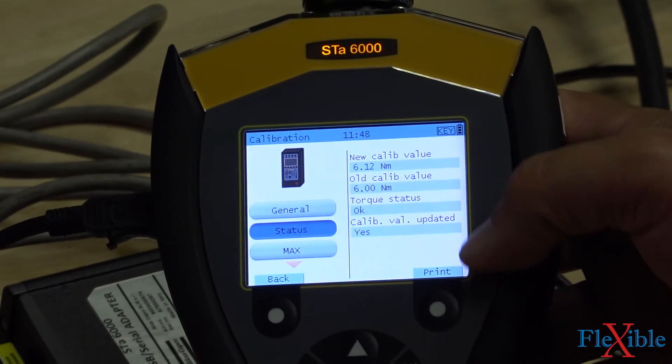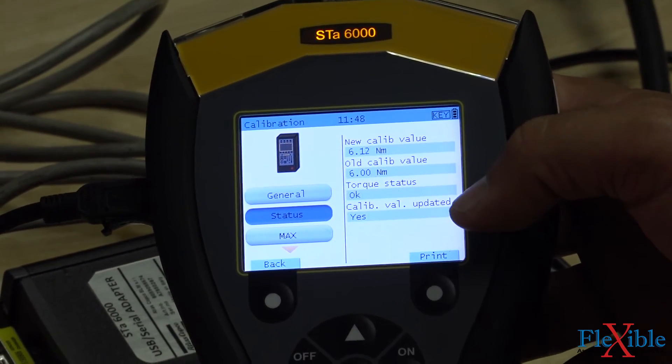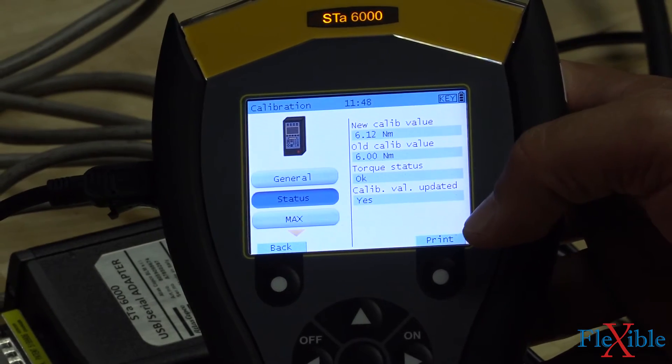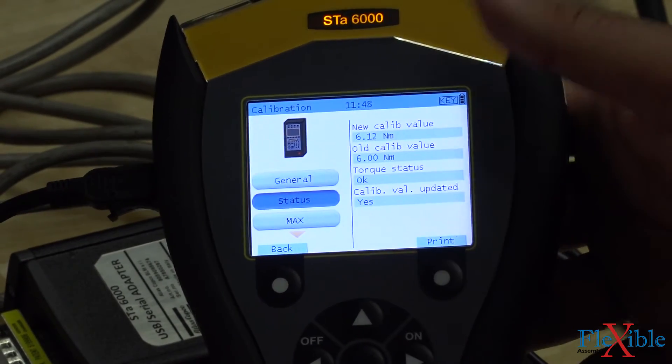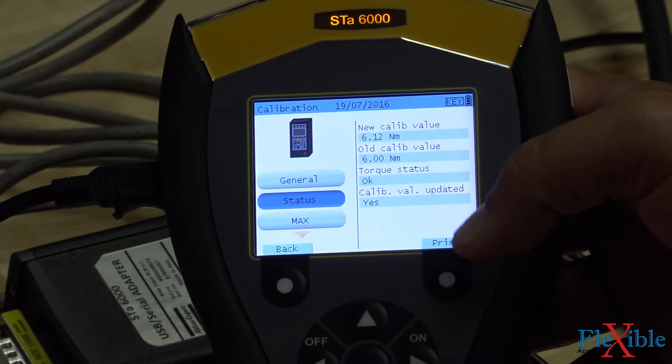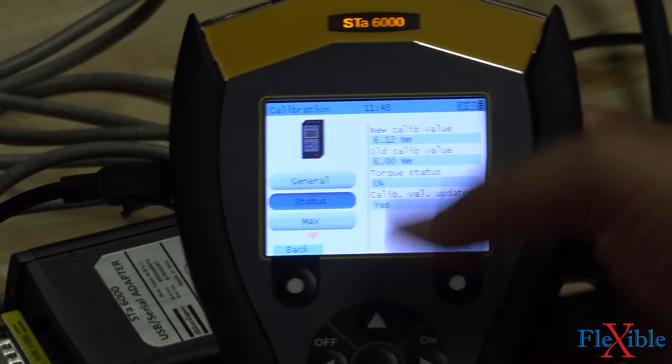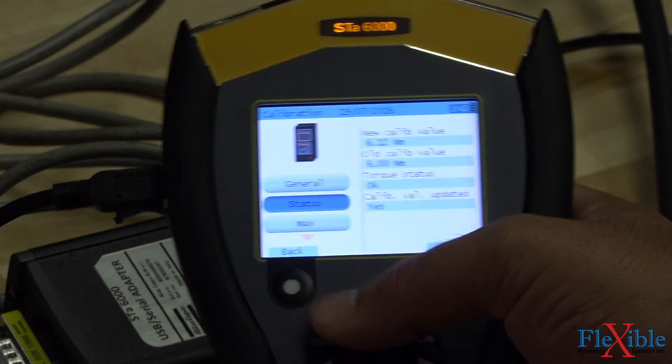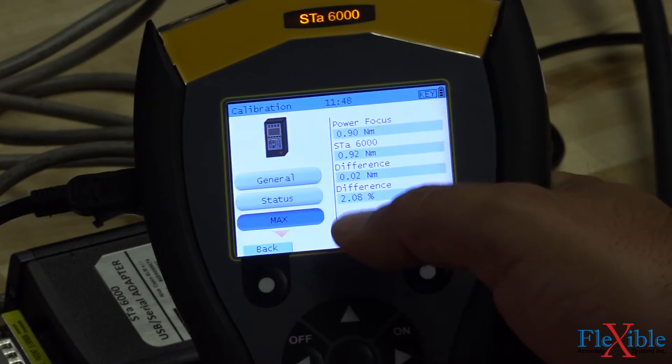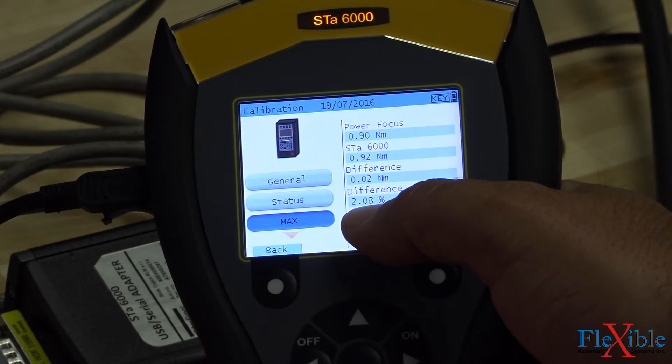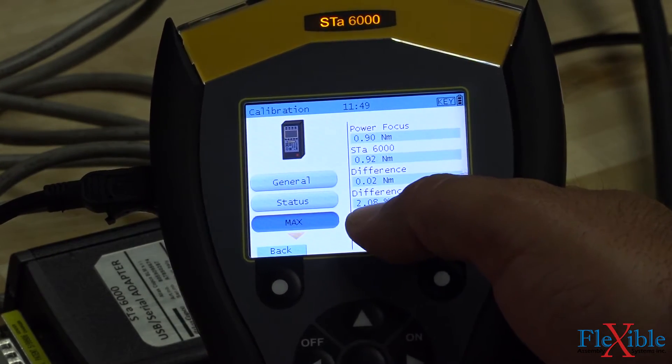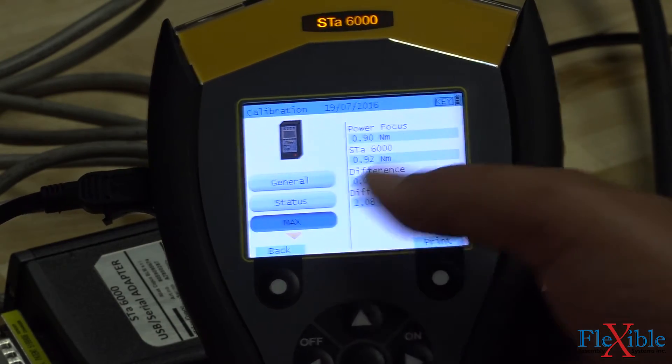If we hit cancel after our calibration, the value would not have updated, but the report would still save. Under the max tab, we can see the difference was only 2.08%, well within our 5% limit, meaning the tool has passed.